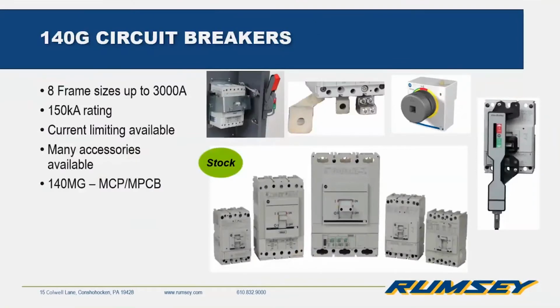Okay, 140G molded case circuit breakers. So 8 different frame sizes up to 3,000 amps. And we can get some of them up to 150 kA interruption rating. There's also current limiting available. So the H frame at 125 amps, the J frame at 250 amps, and the K frame at 400 amps can all be ordered with current limiting capabilities. And the many accessories that you're used to, flange mounted disconnects, terminal lugs, rotary handles through the door, flex cable, all of those things are available.